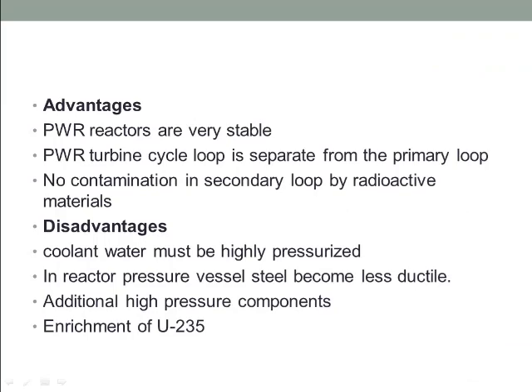There are two main advantages of the pressurized water reactor. First, pressurized water reactors are very stable due to their tendency to produce less power as temperature increases, making the reactor easier to operate from a stability standpoint. Second, the pressurized water reactor turbine cycle loop is separate from the primary loop, so the water in the secondary loop is not contaminated by radioactive materials.